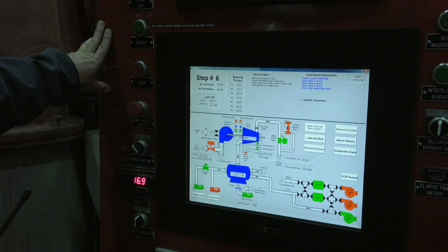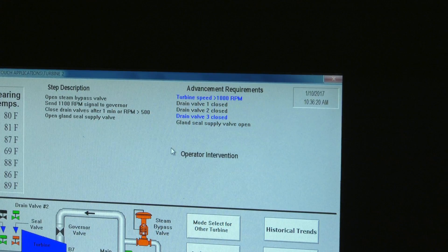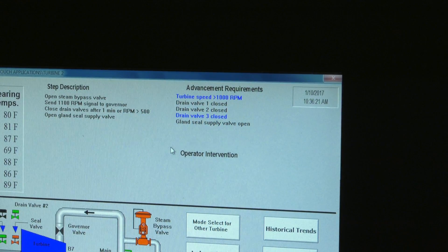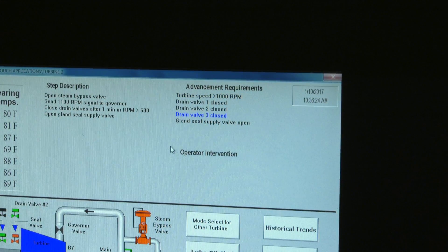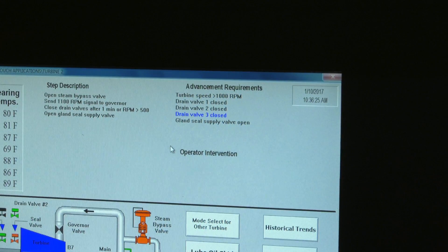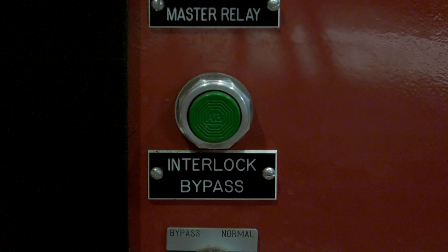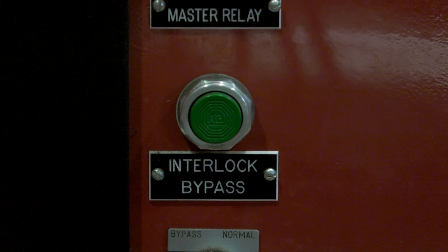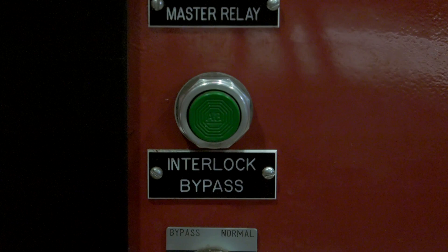It is important to know that any step that has not been completed will be blinking in blue in the upper right-hand corner of the MMI. Once the step is complete, the lettering will be black. The PLC can be manually advanced by pressing the interlock bypass button on the front of the turbine control panel.